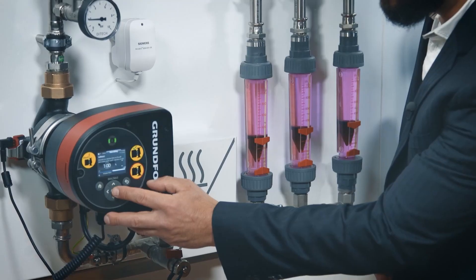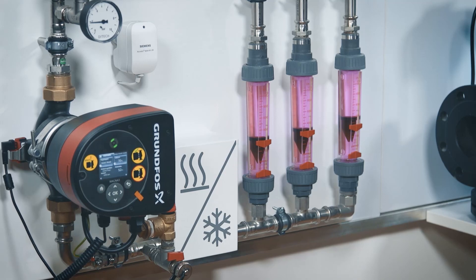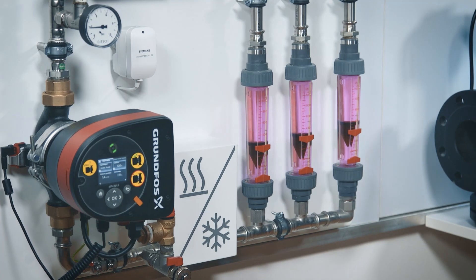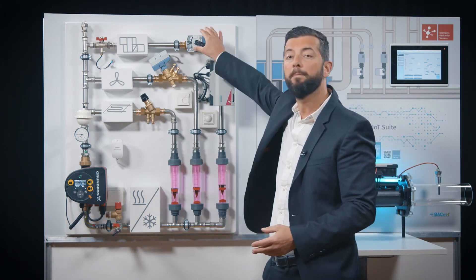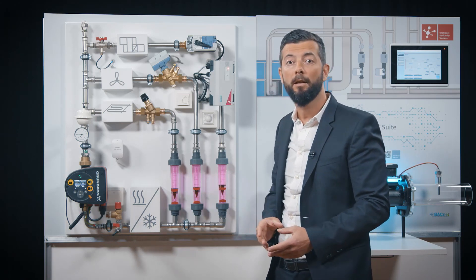Now I'm going to go from 70% up to 100%. And as you can see here, the flow rate in the circuit controlled by the PICV has basically not changed, even if the pump is now pushing much stronger than before. But have a look at this circuit controlled just by a static control valve. If you do the math here, you have 40% more flow.